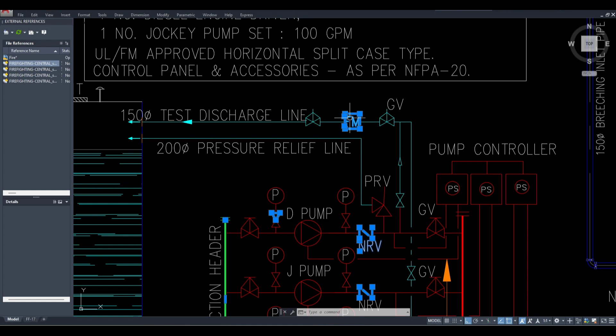Now whenever you connect a flow meter, it depends on the manufacturer, but normally it has to be in a completely straight line, because of turbulent and laminar flows, maybe you have studied in hydraulics. The water should flow in a steady way, then only can it measure the reading correctly. That's why we don't want any bend immediately. So what is the rule? Five times the pipe diameter at the back and three times the pipe diameter at the front. Straight length means there should not be a bend, tee, or 45, nothing like that.